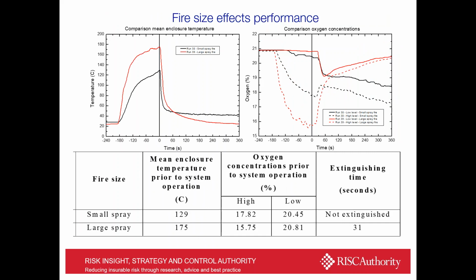Fire size affects performance as well for exactly the same reasons. So here we have two spray fires, a small and a large. And again, on the left-hand side, you can see that the mean enclosure temperature gets up to about 175 degrees for the large spray fire and only 129 degrees for the small spray fire. Likewise, the oxygen concentration for the large spray fire drops down to around 15 or 16%, but for the small spray fire to 17 or 18%. And the difference here is not just a change in time, but for this ventilation configuration, it's a difference between extinguishing the fire and not extinguishing the fire. And again, this is a deviation possibly from what we're used to. We're used to systems which do not really behave in a binary fashion. We like to see a change of performance, but not a major difference, such as whether it gets extinguished or not.